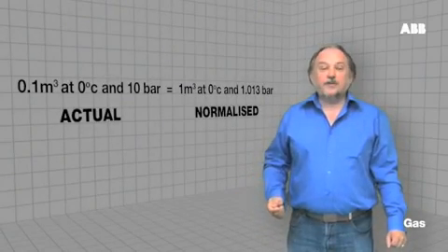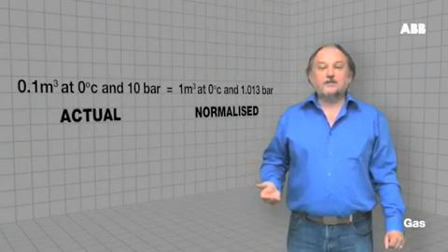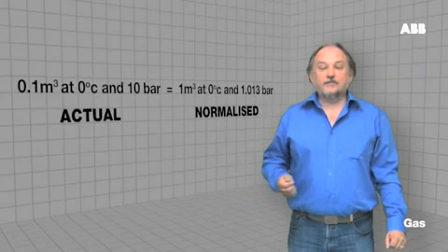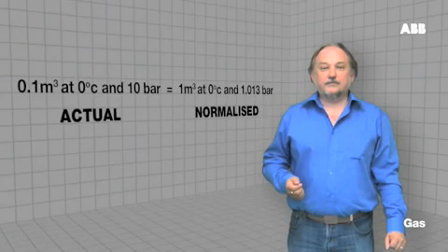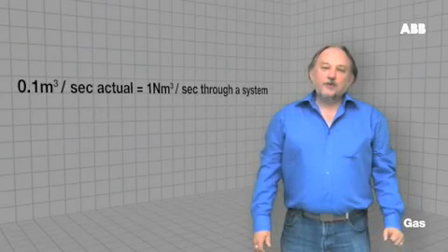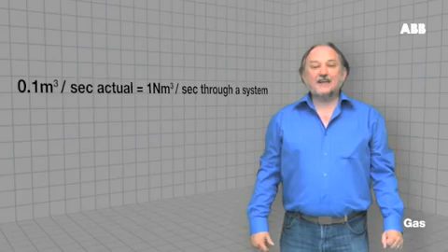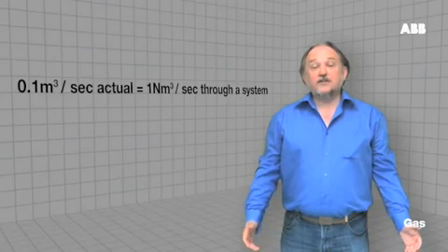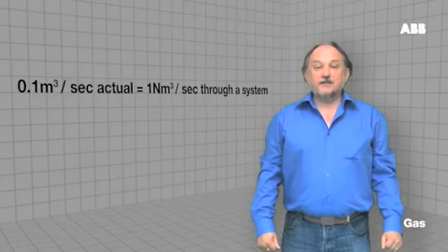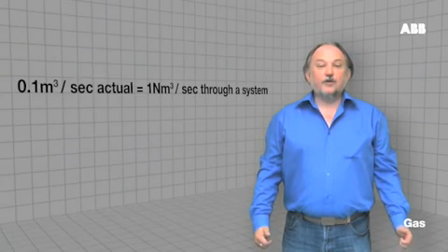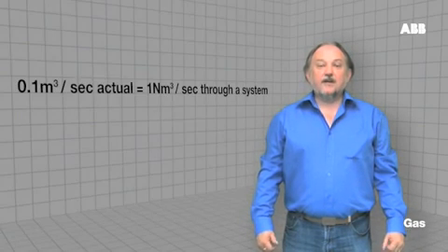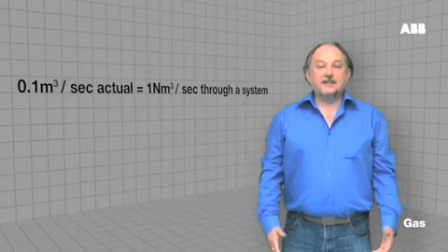Here we have an example of the comparison between normalised volume and actual volume. If we run both of these volumes through a system, 0.1 cubic metres actual per second is actually equal to one normal cubic metre per second. The volume flow is different in both cases. However, the mass flow rate is identical.